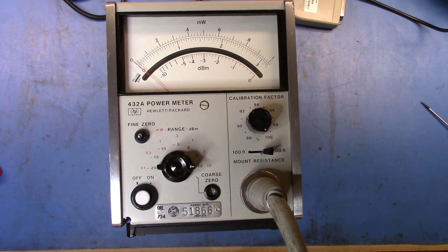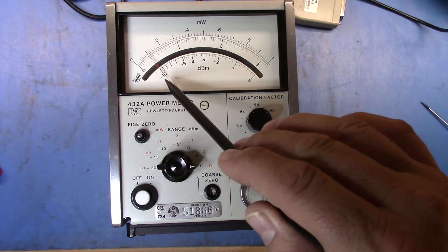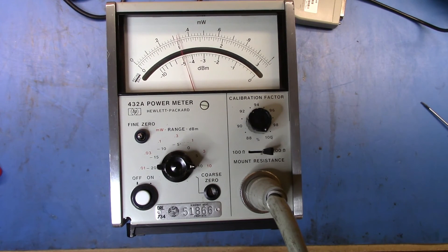Let's turn the RF off, go all the way back over, we'll zero this again, turn the RF on, now let's step it up. We shouldn't see anything until we hit about zero dB, and there we go. We're at minus 10, minus 5, and zero. Now we don't know how linear—I'd have to look at the calibration data for my 8657B. These items can also be calibrated, so we don't know when it was last calibrated. But overall, it looks like we have a pretty much working unit. I'm quite happy with that.